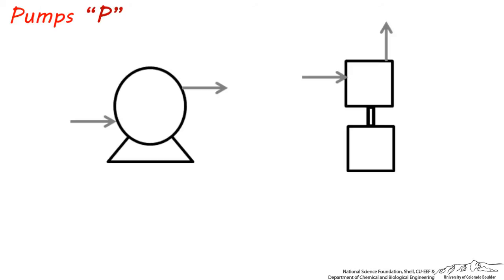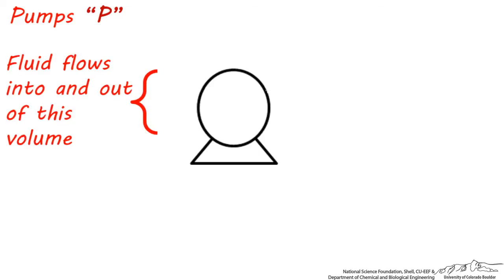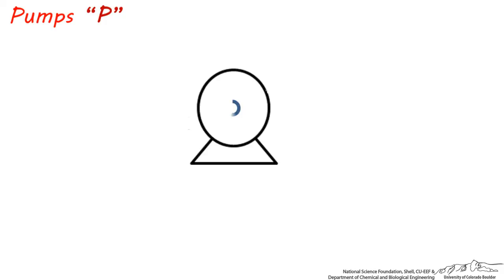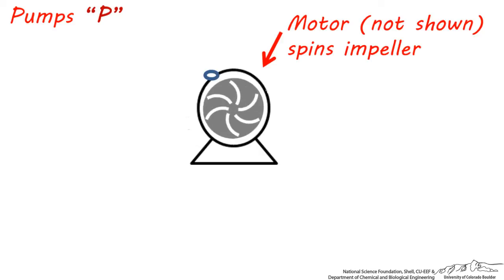So you can understand how these units function, let's briefly look at some key parts. This symbol is usually a representation of a centrifugal pump. This circle represents the volume the fluid flows into and out of. This bottom portion is the stand the pump rests on. Fluid usually enters the center of the pump and will exit perpendicular to the inlet. On the inside, there is an impeller which rotates at hundreds or thousands of revolutions per minute. Behind the pump, there is a motor, which is responsible for spinning the shaft that rotates the impeller.